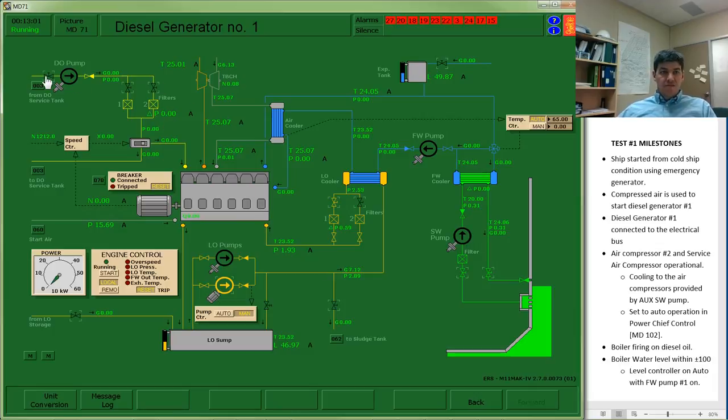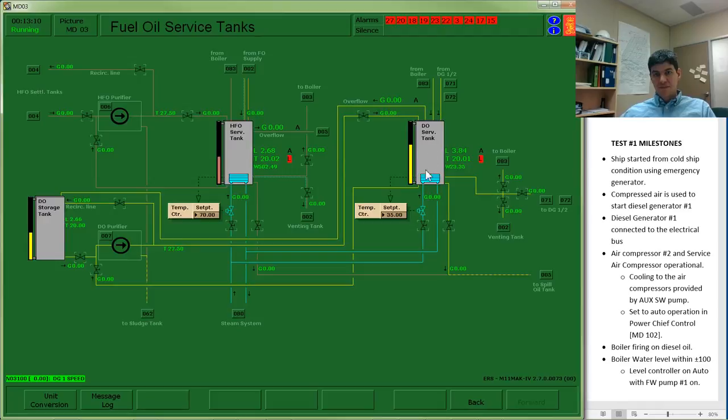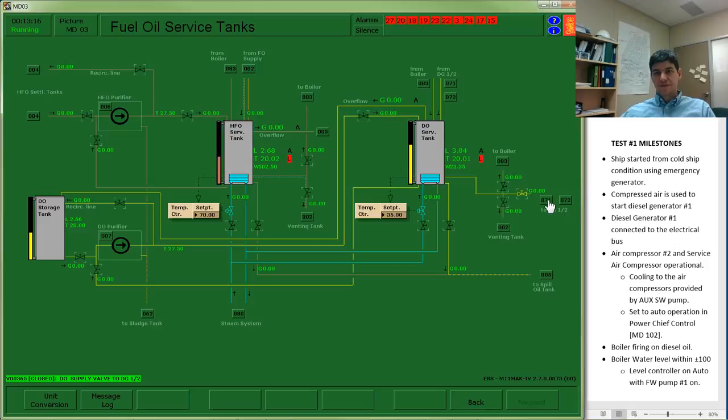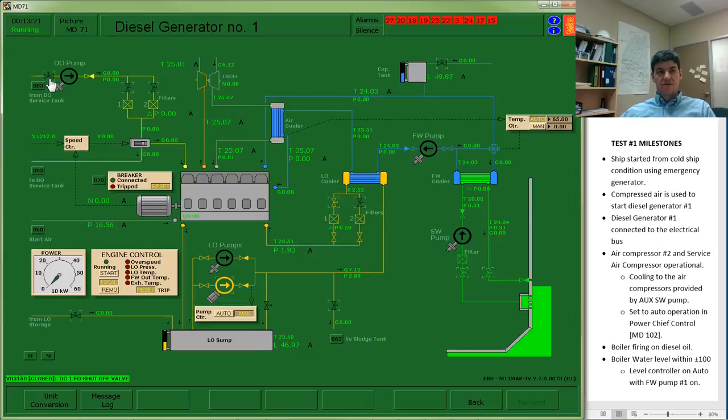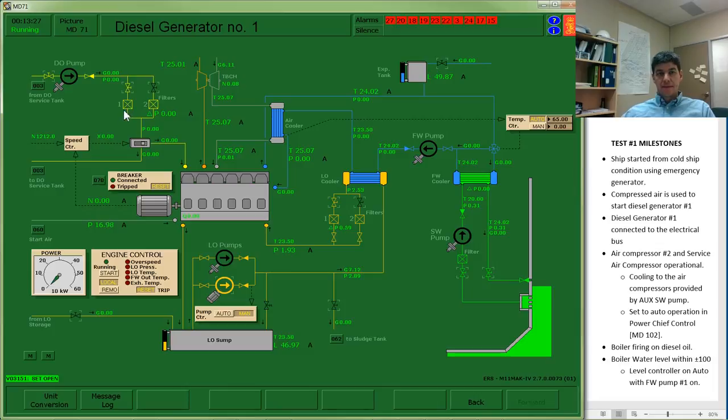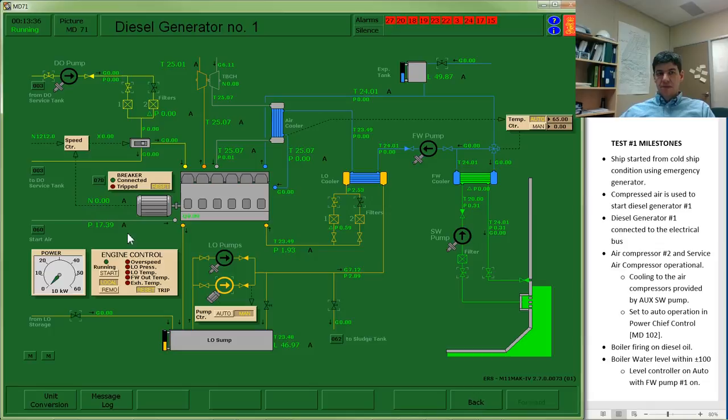I also have my diesel oil pump and fuel system. So I'm going to start from my source, diesel oil service tank, and then work my way through, open up the valve to get to the diesel generator 1 and 2. That brings me to here. I've got a valve, and then I have a valve as well in front of the filter. I can confirm that my pressure is now above 15, which is the target for it to be able to start.